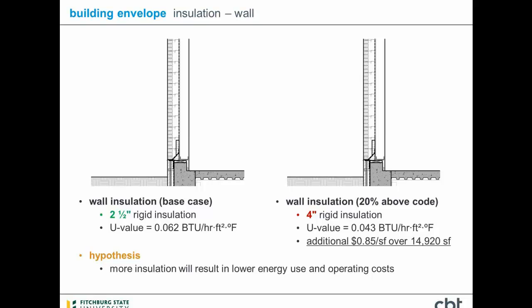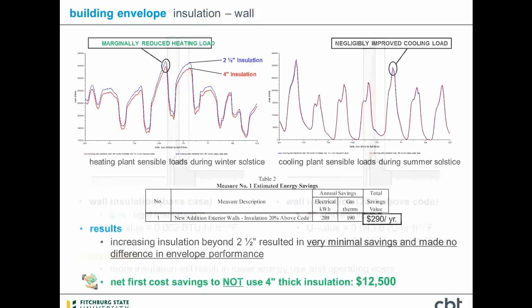The first of these we looked at was the exterior building insulation. One simulation was run using the code required minimum 2.5 inches of rigid insulation, and we compared that to a simulation where we ran it with 4 inches of insulation, which was a 20% above code increase. The assumption being that by spending a little money up front on additional insulation, we improve the operating performance and cost of the building moving forward.